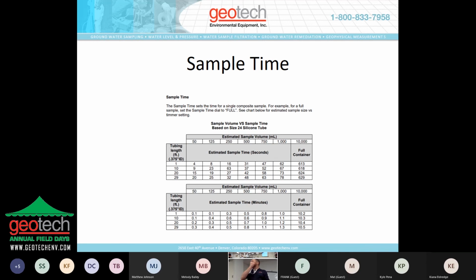So the length of time that it needs to be on is dependent on how long the tubing is and how much sample volume you want to collect. For example, if we wanted to get 500 milliliters and we had 10 feet of tubing, we'd have to set that to 37 seconds. You'd use this as a ballpark to get you close to where you need to be, and then ideally use a graduated cylinder, run the pump, and fine tune the dial to exactly what time you need it.